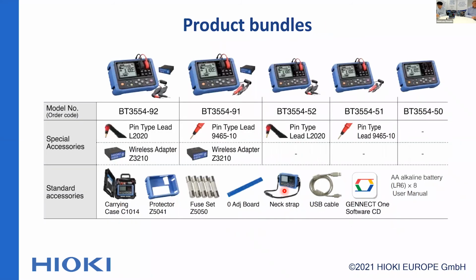Okay, this is the product bundles. Here are the lineups. You can choose between two types of probe kits, L type or straight type, and with or without the Bluetooth function. As an accessory, 5 spare fuses are included in all kits. If the fuse is not used, there is a risk that the protection will not work properly and the unit will break, so please be sure to use this fuse. That's very important to protect against high voltage.